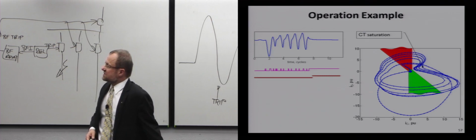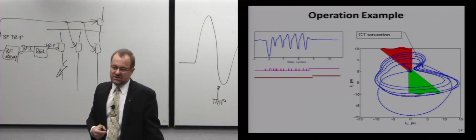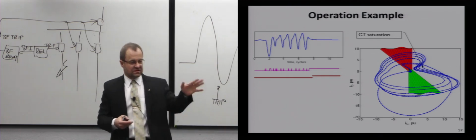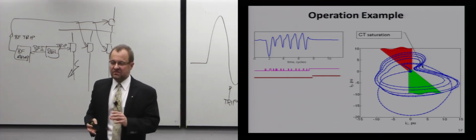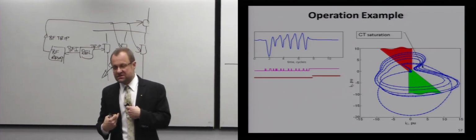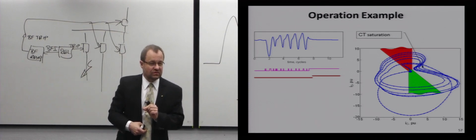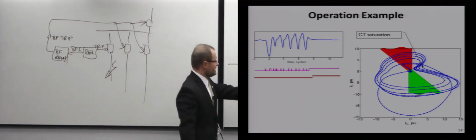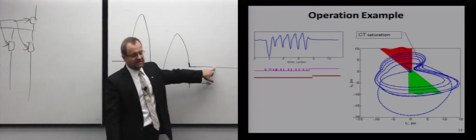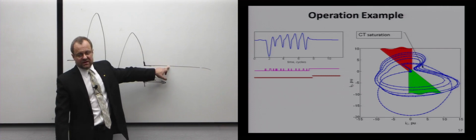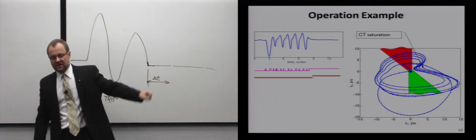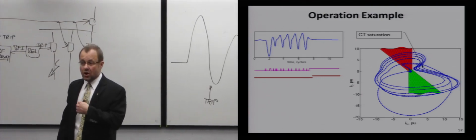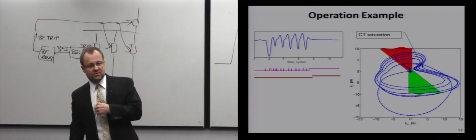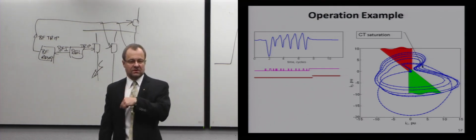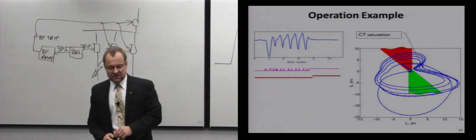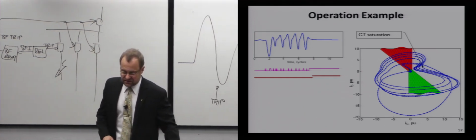By the way, with that current transformer saturation, there are two of them. Normally, we just blame the CTs and say CTs saturate. The truth is that it's a little bit of both. We have a CT inside our box, and that CT could saturate a little bit too. So that subsidence current, the fact that the breaker interrupted at the zero crossing and the primary current is dead zero, but we are not measuring that zero. The fault for that is the main CT out there in the switchyard, and a little bit is our own CT inside the box, the one that we put there for galvanic isolation between our electronics and what is happening in the switchyard.